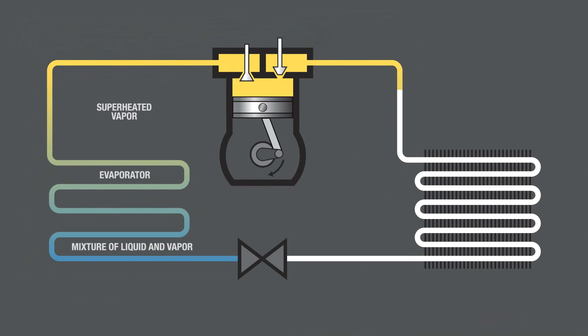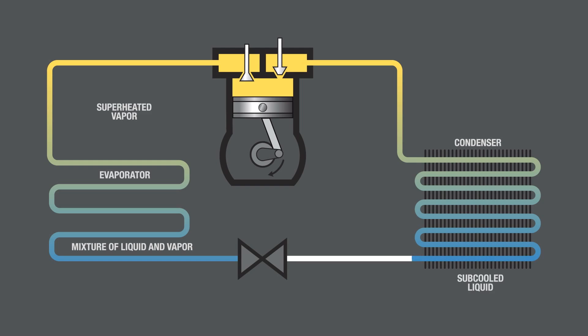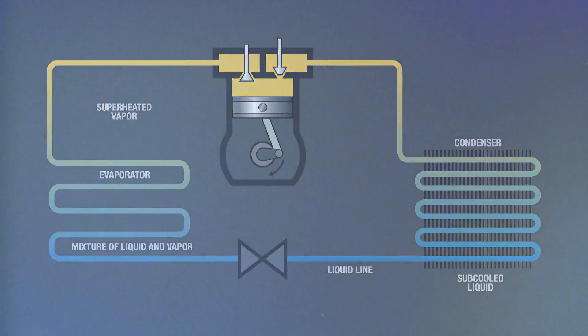As refrigerant enters the system's condenser, it's in a vapor state. As heat is removed from the vapor, it will turn to liquid at its saturation condensing temperature. After the vapor has turned to liquid, any temperature of the liquid below this saturation condensing temperature is called subcooling.